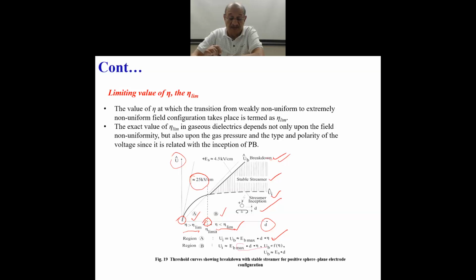And in region B, what is the maximum electric field intensity in the electrode system can be estimated with this equation. UB, the partial breakdown inception voltage, will be equal to EB max into d into eta. That means UB here is a function of eta, but UB in an extremely non-uniform field cannot be estimated with the Schweiger factor eta, but the inception voltage of partial breakdown can be estimated to a great extent in an extremely non-uniform field configuration.